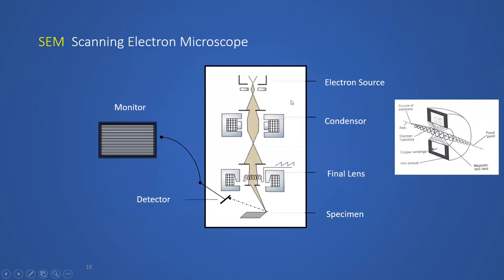So this is again a schematic of the different components of an SEM. This is the electron source, these are your condenser lenses, and the C3, condenser lens 3, is also called the final lens. The other important thing to note here is that, I'm not sure whether you've had your confocal microscopy classes yet, but there is something called rastering. So here, the beam is rastered, scanned over the specimen line by line like this. The electron beam moves left to right, then comes again, moves in the y direction, and again moves across. So line by line raster scanning over the specimen is similar to confocal microscopy, where the laser beam is also raster scanned over the specimen using galvo mirrors. So here it's a similar thing.